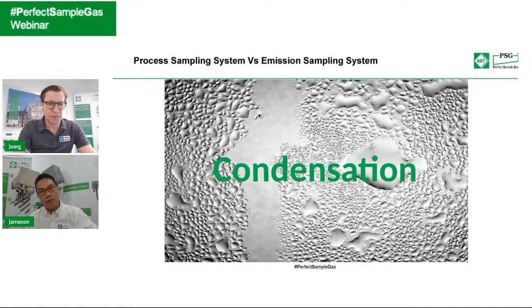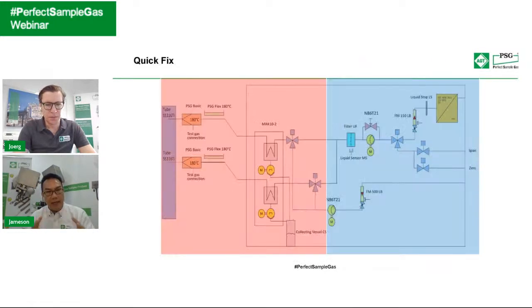Regardless of whether the process temperature is 500 or 50 degrees, our purpose is to maintain the sample temperature inside the sample probe at 180 degrees, above the water and above the acid dew point. I think this also shows it pretty well, James, in this overview slide, right? And this is the complexity, the two worlds we live in.